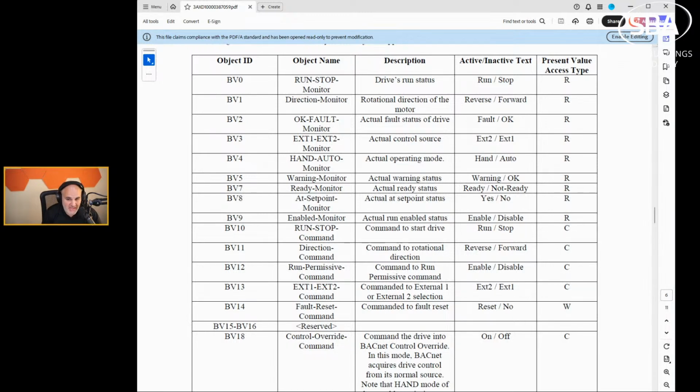We're going to go through subnets. We're going to go through IPv4. We're going to go through understanding when I say that BACnet IP is a UDP connectionless protocol. It's a layer 4 protocol using BVLCs and BACnet virtual links and all that jazz. I will explain that to you so it makes sense, so that then you can understand, oh, that's why we use BBMDs. That's why we use BDTs. That's why UDP port 47808 matters. And if there's a mismatch there, that's what causes the issues.